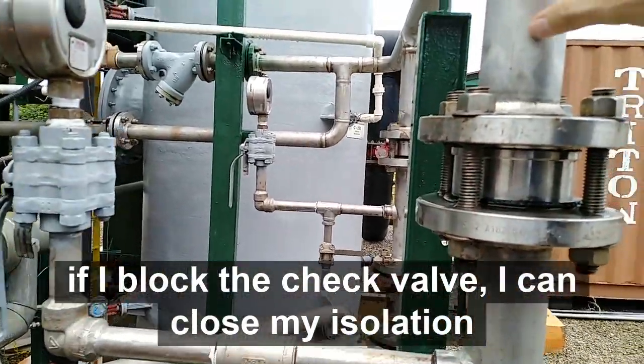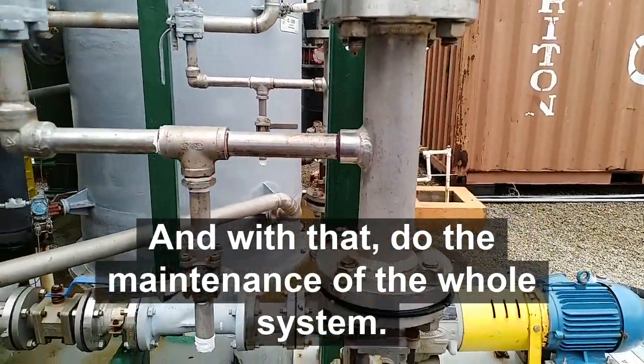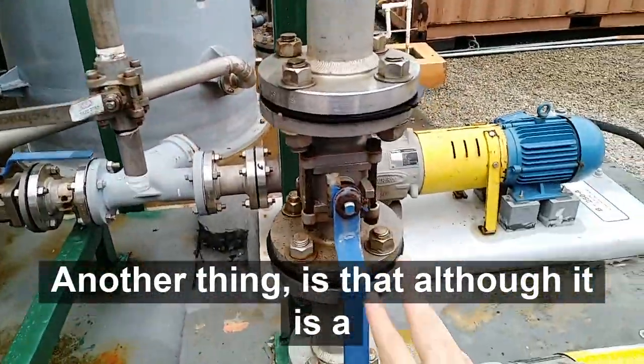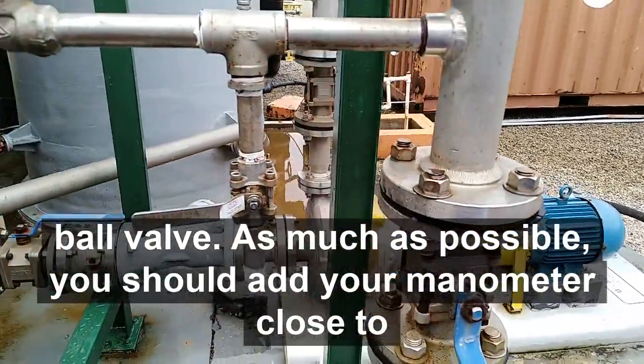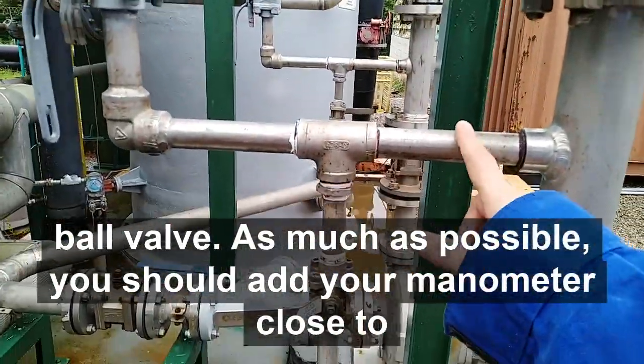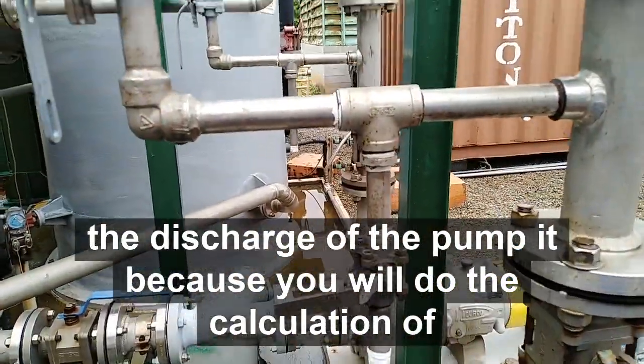because if I have some kind of stuck or impingement — if the check valve gets blocked — I can close my isolation valve and then do the maintenance of all of this system.